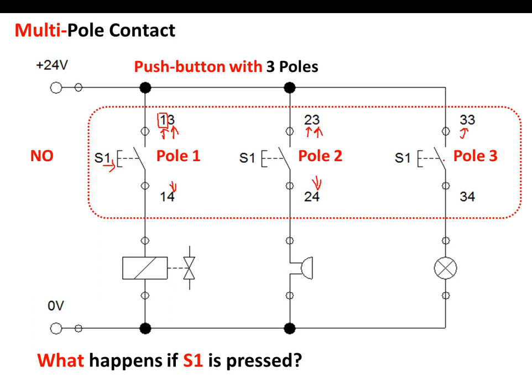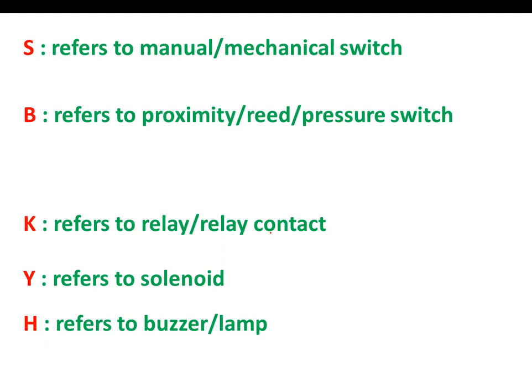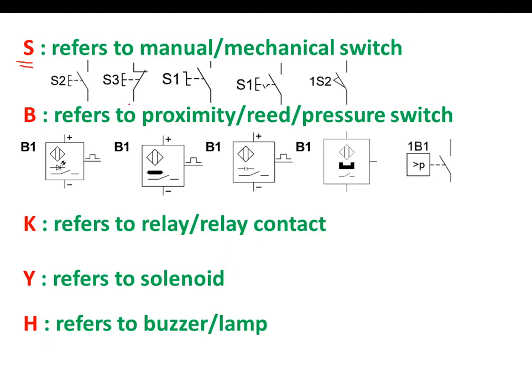We need to be familiarized with the new symbols in electro-pneumatics. S refers to any manual or mechanical switch — whether normally open, normally closed, set button, or roller lever valve. B refers to any proximity switch such as optical switch, inductive switch, capacitive switch, reed switch, and pressure switch. K refers to relay coil and relay contact. Y refers to the solenoid, while H refers to a buzzer or lamp.